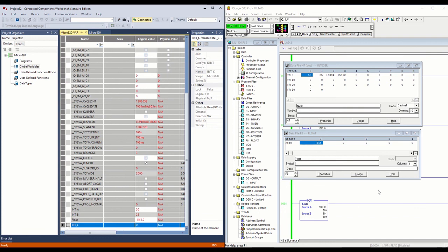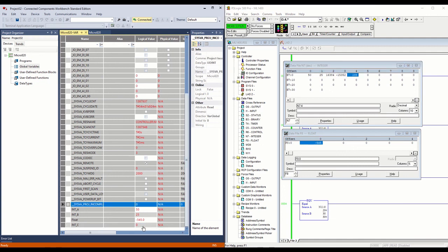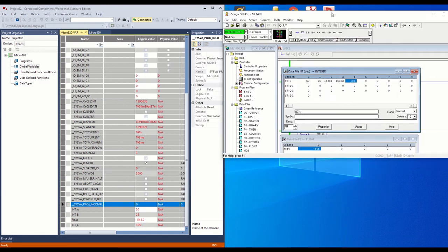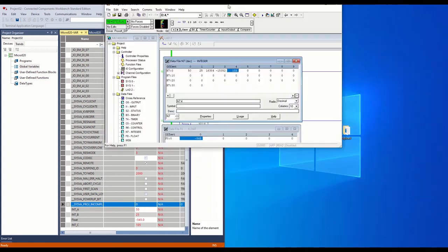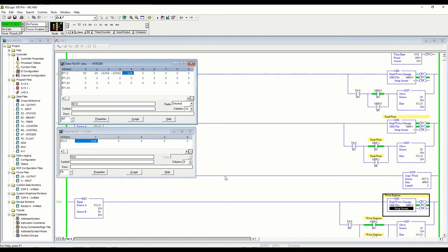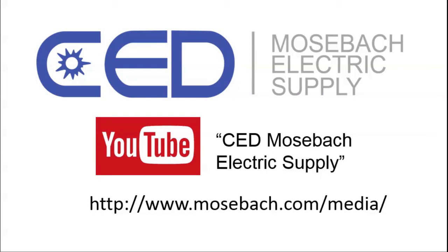This last one — integer C — is the one we're writing from the MicroLogix to the Micro820, and that's our N74. If we change this value here we should see it update over there. There we go — there's our 105. So our message commands are all working. The Micro820 here is simply acting as our slave device — it could be any Modbus device in your system. This shows you how the MicroLogix 1400 can act as a Modbus master. Thank you for watching, and don't forget to subscribe to CED Mosebach Electric Supply on YouTube or visit www.mosebach.com/media.